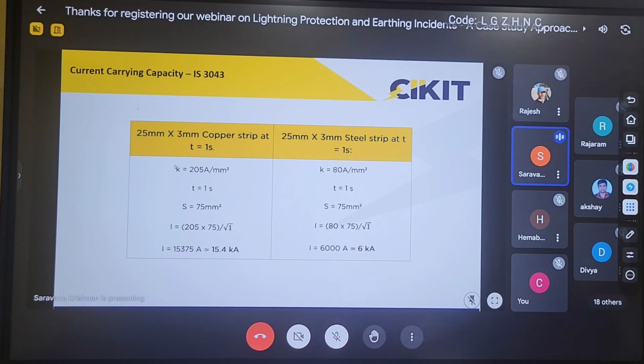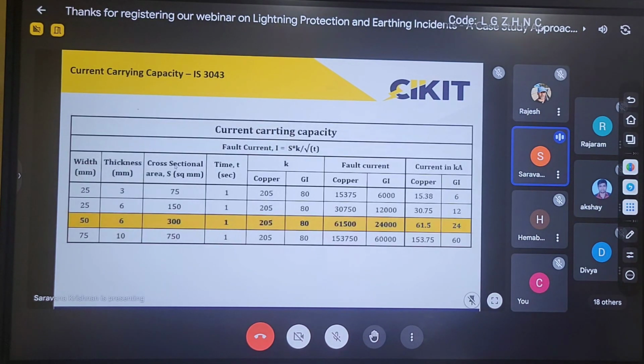So in this particular site condition, they have used a 50/6 copper strip. Instead of the 50/6 copper strip, they have used only a 50/6 GI strip. So if I take this formula into account, the fault current rating for the 50/6 copper will be around 61 kA, whereas if I am going for GI, it will be only 24 kA. There is a huge difference in the current carrying capacity. So if I am changing the material from copper to GI, then I should not consider the cross-sectional area, whereas I need to consider only the current carrying capacity of the particular conductor which we are using.